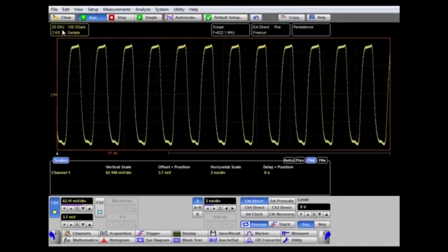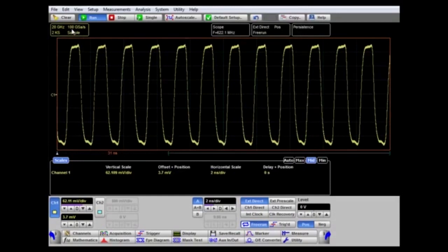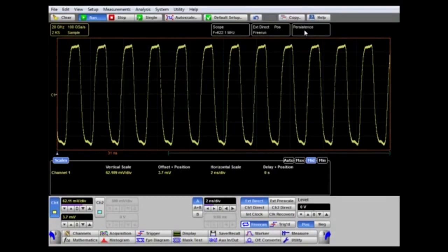More information is shown at the top of the screen about the waveform acquisition. Here we can see the analog bandwidth is 26 gigahertz, the equivalent sampling rate on this time base setting is 100 giga-samples per second, and the acquisition record length is 2 kilo-samples. Also shown is information about the display mode — in this case, persistence.